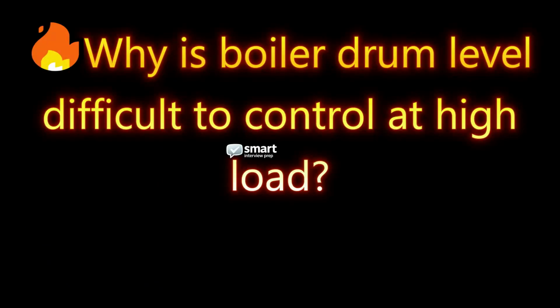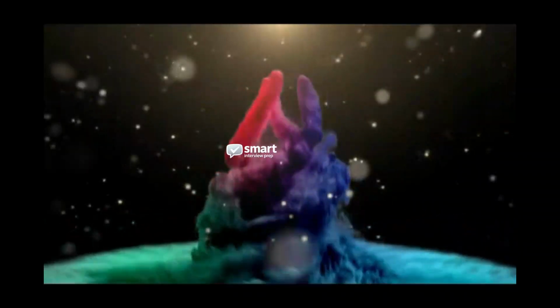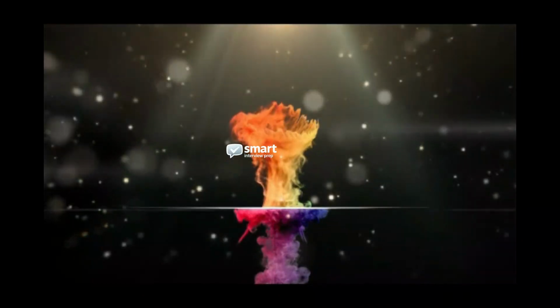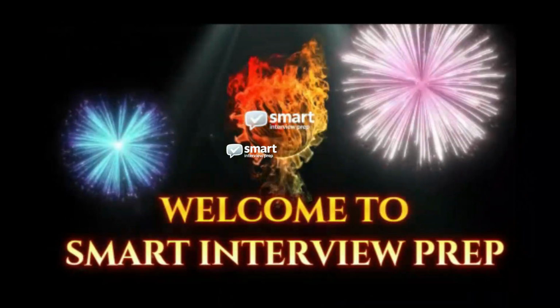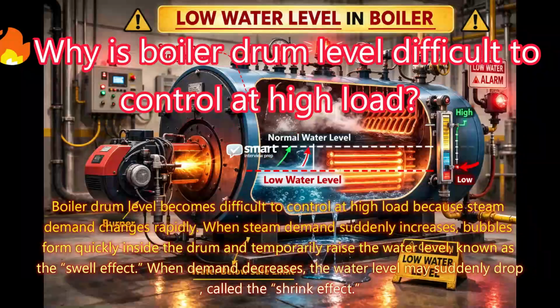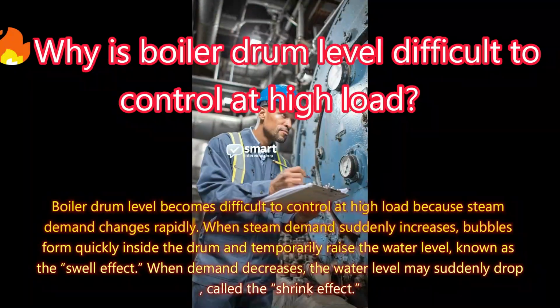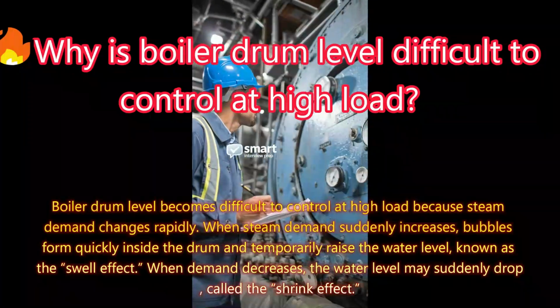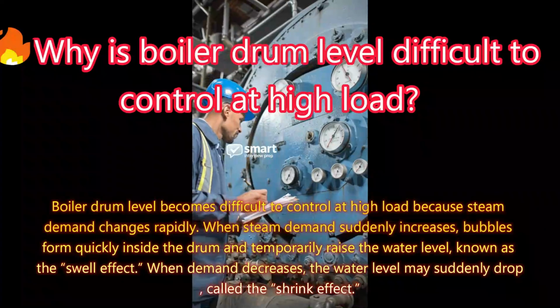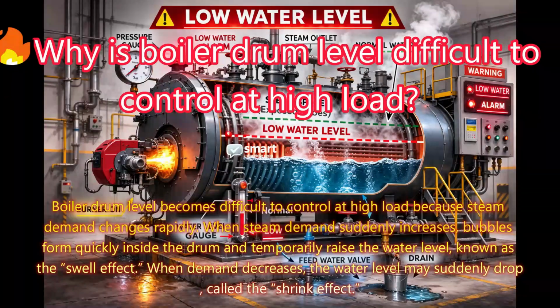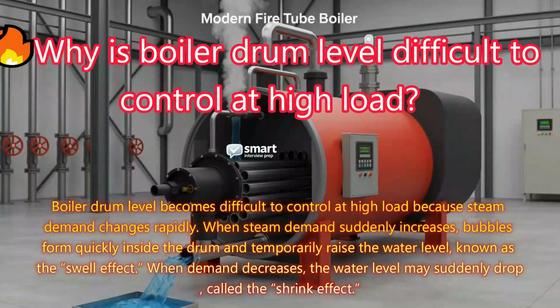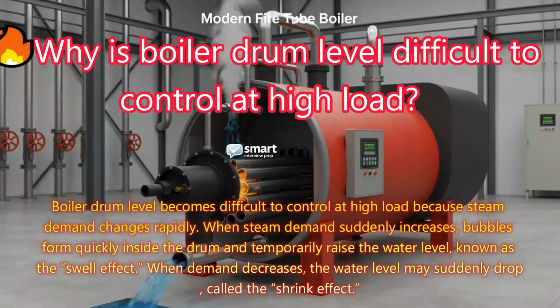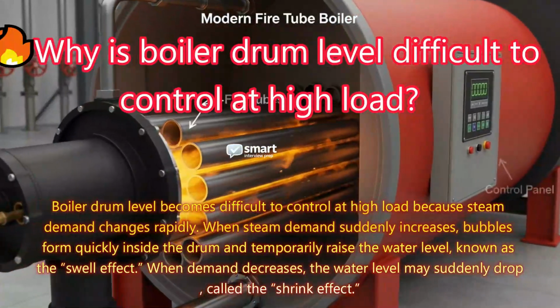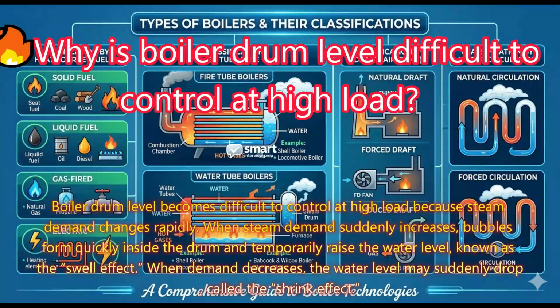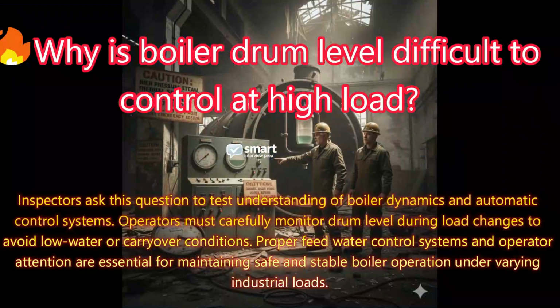Why is boiler drum level difficult to control at high load? Answer: Boiler drum level becomes difficult to control at high load because steam demand changes rapidly. When steam demand suddenly increases, bubbles form quickly inside the drum and temporarily raise the water level, known as the swell effect. When demand decreases, the water level may suddenly drop, called the shrink effect.